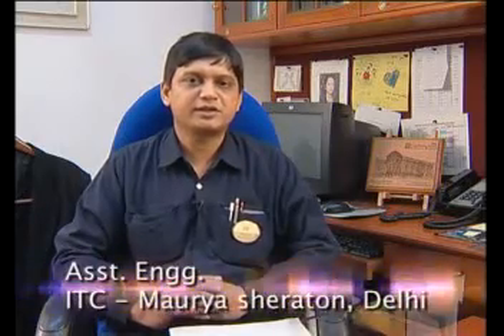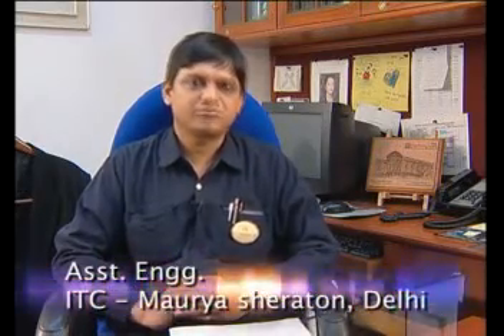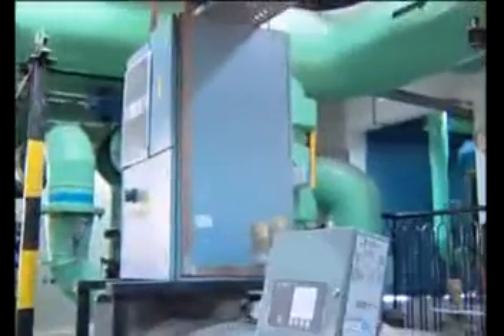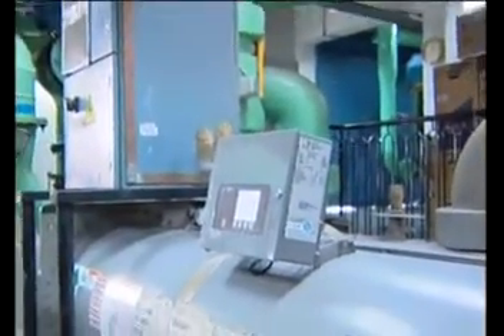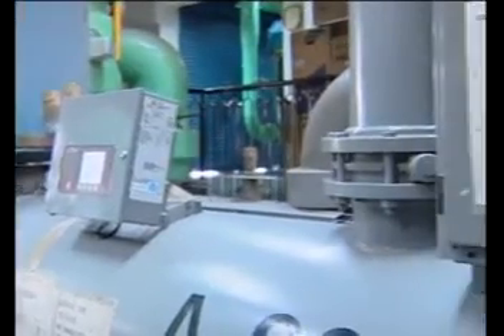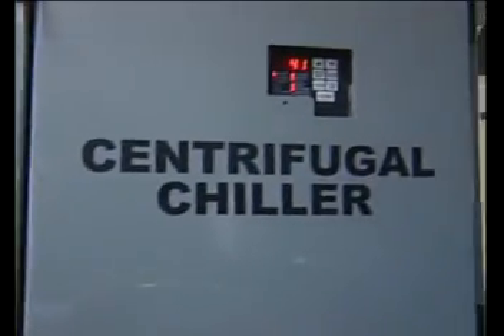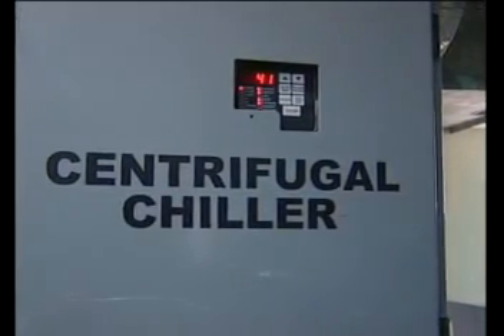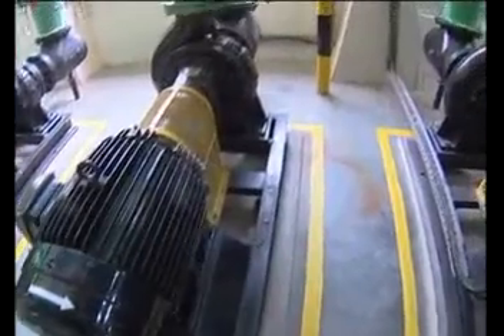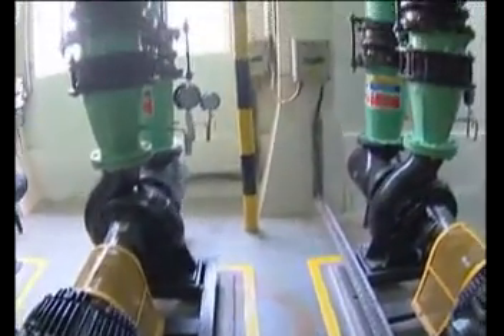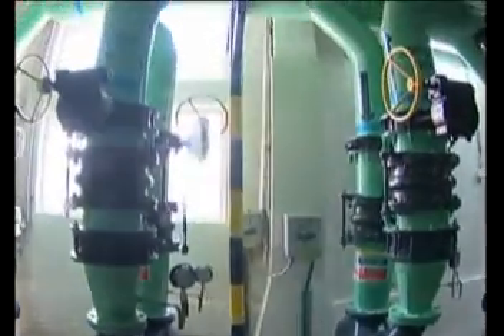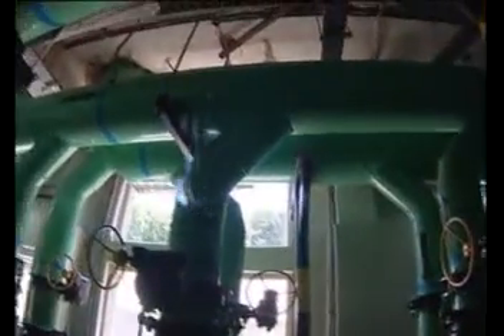We have replaced two aging 300-ton centrifugal chillers with the most recent state-of-the-art variable frequency driven centrifugal chillers. The kW per ton of these new centrifugal chillers is 0.62 when compared to the earlier aging centrifugals at about 0.8. We also moved away from the conventional pumping systems to primary and secondary type of pumping systems.